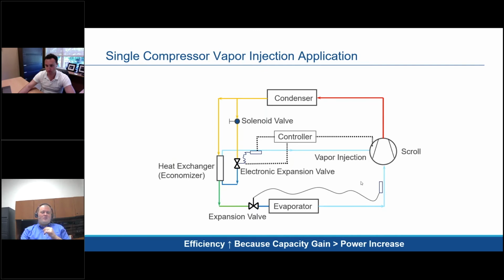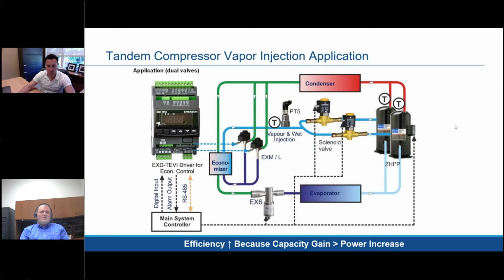I'm going to be showing a Tandem coming up here in a little bit, but the OEM for the system, they would be installing these lines within their system in order to get that extra capacity out of that condenser that they would need. Here's a little bit more detailed. We have Tandem offerings as well. So it's doing the exact same thing, except you're doubling the compressors. You have 2 expansion valves in there, and the solenoid valves are closer to the compressor, so you can isolate them better as well. There's a controller that they can use.